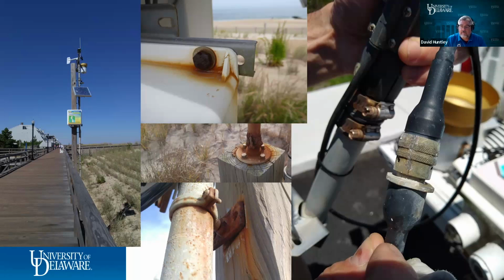But then you also have some material selection problems. That top middle picture, when we replaced the enclosure, we used to get enclosures that came with all stainless steel components, and I didn't check this one. When we installed it, that was a brand new box. That picture with the rust on it is less than six months old.